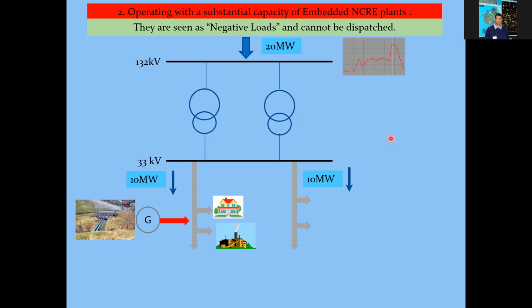For example, now in our country, the spinning reserve policy is 5%. We must always have 5% of spinning reserve. Spinning means they are ready to be taken up. They are not fully loaded. The capacity is there, on the positive side as well as the negative side. So when system operators are operating the system, they are mindful that what you just asked can happen. Sometimes about 50, 60 megawatts, even when one large 33 kV feeder trips, one feeder can go up to 20 megawatts, because these feeders are about 400 amperes at 33 kV. So if one fully loaded feeder trips, the load comes down by 20 megawatts. So system operators always keep a margin in their hands to play around with increasing and decreasing loads. So yes, we do that. We are keeping a margin in generators. Thank you, sir. Got it.